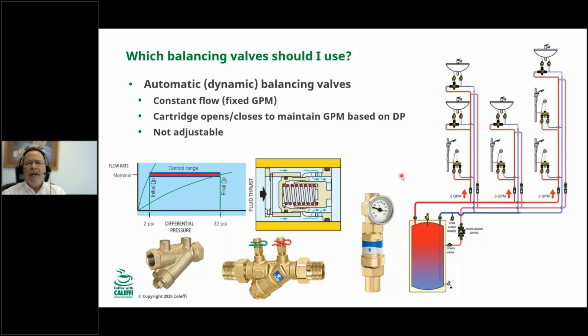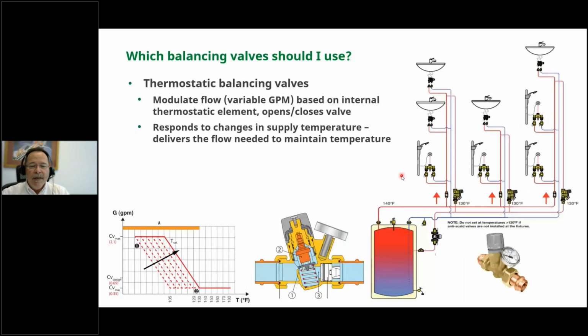The third type is a thermostatic balancing valve, relatively new in the industry, but really gaining a lot of traction. These are my favorite, and I'll show you why. These valves modulate. So if you look at this graph in the lower left-hand corner, on the bottom on the x-axis here is temperature. So when the water coming into the valve is cool or cooler than the adjustment on this set point knob or the pre-calibrated cartridge, the valve opens.